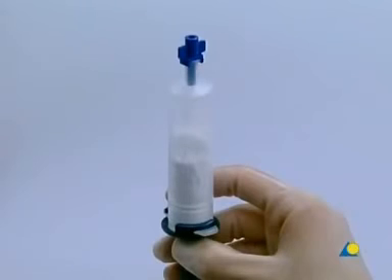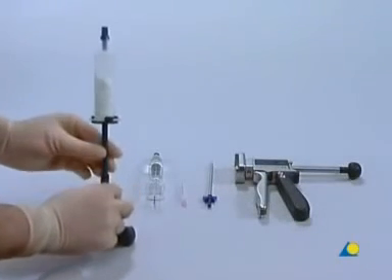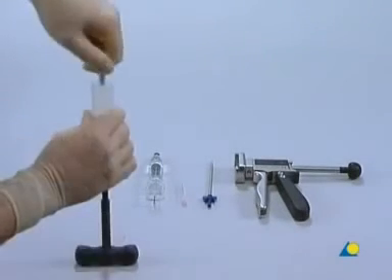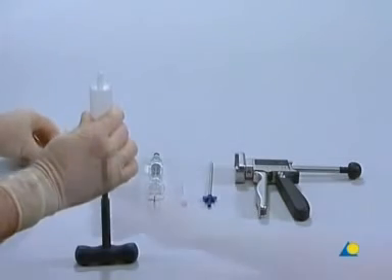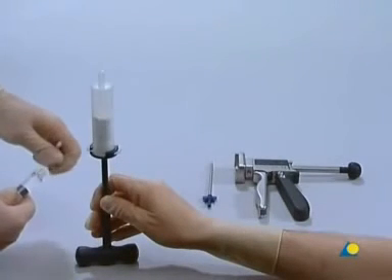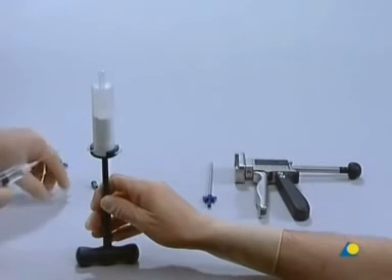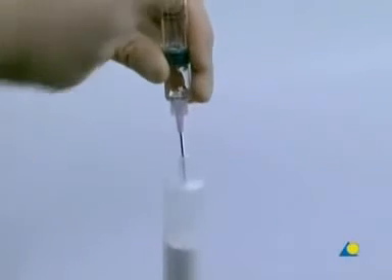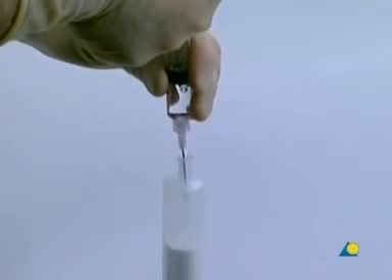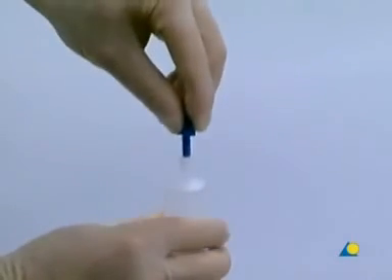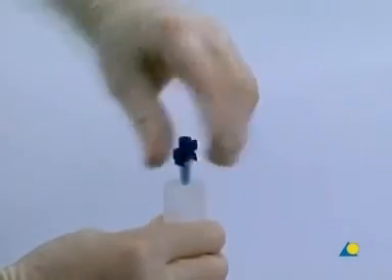The Chronos inject powder is supplied in an application cartridge. Tapping the application cartridge is necessary to make the powder fall into the base of the cartridge. The blue sealing cap is removed. The blunt injection needle is mounted on the syringe containing the liquid component. All the liquid is injected into the cartridge. The blue sealing cap is replaced and locked by its bayonet catch.